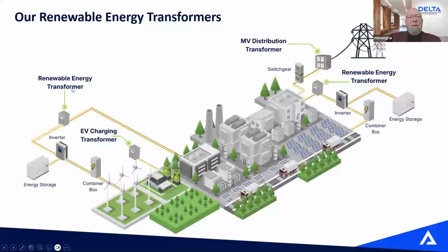So that's why when we build a renewable energy transformer, we don't label the windings primary and secondary. We label the windings grid side and inverter side. So you know that you need to connect the grid side to your building and the inverter side to your inverter. Again, depending on your voltage, your building might operate at 600Y/347, 208, 120. Your inverter might be at 480 volt Y/277, could be at 208, could be at 600. So you may end up with a transformer that has the same voltages on both sides, but you need to know which side connects where.